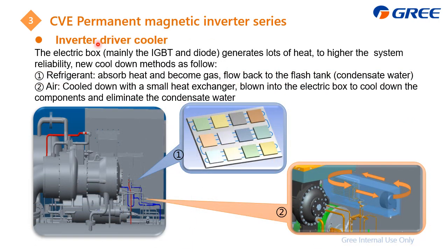For the inverter drive, either the IGBT or the diode will generate lots of heat. So for the compressor drive, we need to set up a device to release this heat to ensure reliability. Here there are two methods. First, we cool it down with the refrigerant, located here. You can find the heat sink, just a bit higher than the driver, and inside it is the refrigerant. The refrigerant will absorb heat, become gas, and flow back to the flash tank.